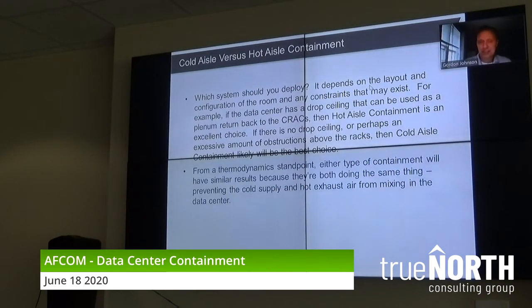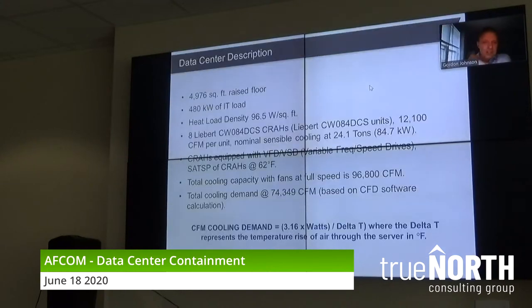You often don't have a choice what type you put in. Most new data centers, as they're being designed and built right now, are choosing to go with hot aisle containment. Most legacy data centers choose cold aisle containment simply because they don't have a choice. Let's look at a case study.